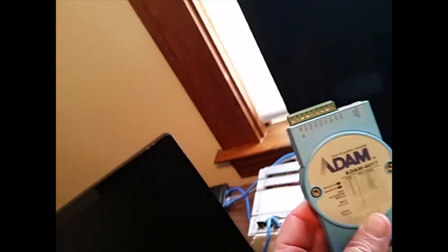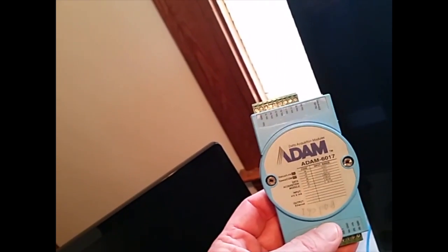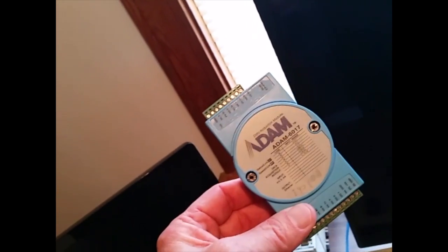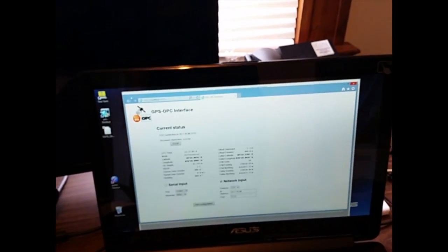So it takes advantage of the PLC system and the instrumentation that's already on the dredge. In fact, if a dredge does not have a PLC, I could simply install this $350 device, which will work. It takes analog input, all 8 channels, so it'll bring in all of your instrumentation that you need and give it Ethernet up into this computer so that there's no proprietary hardware in the field. Don't need all these different serial devices that I've seen on some people's systems.